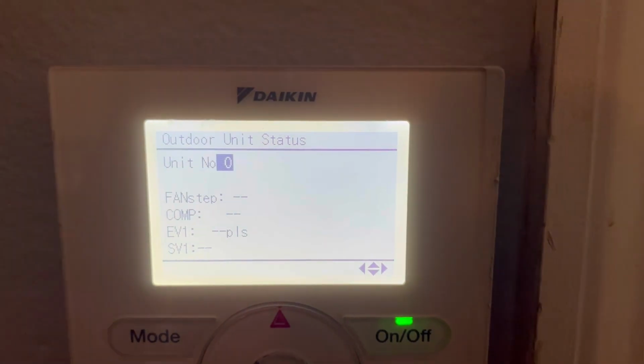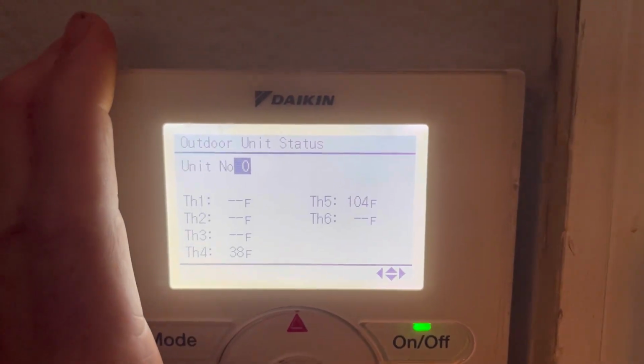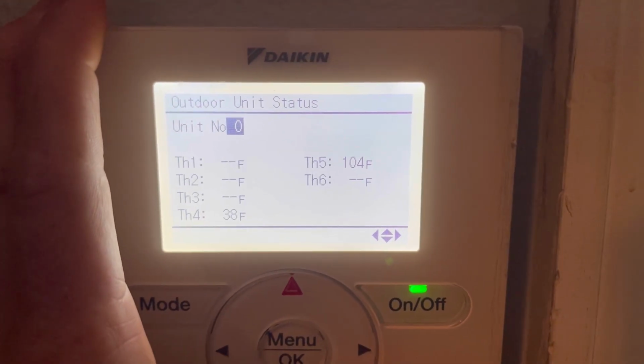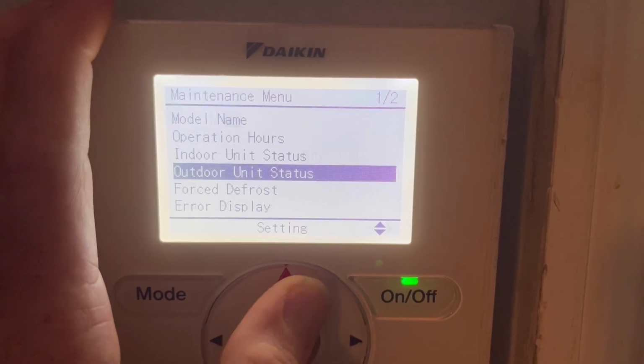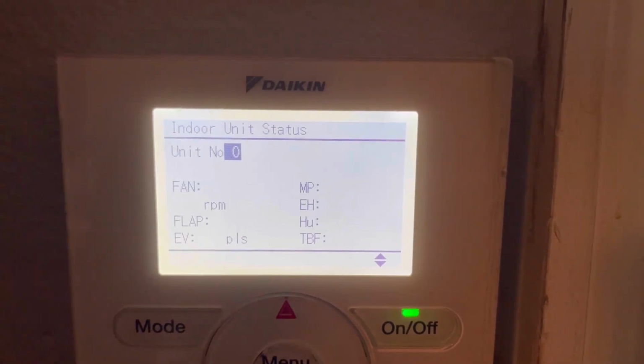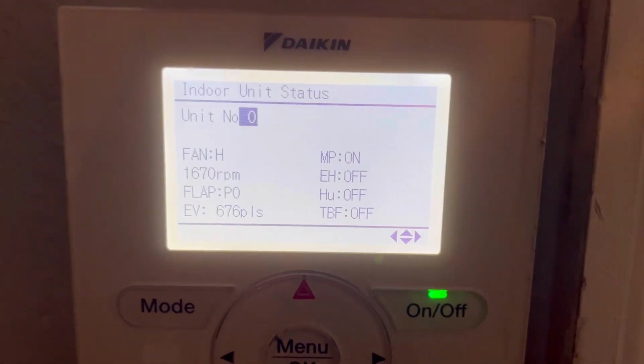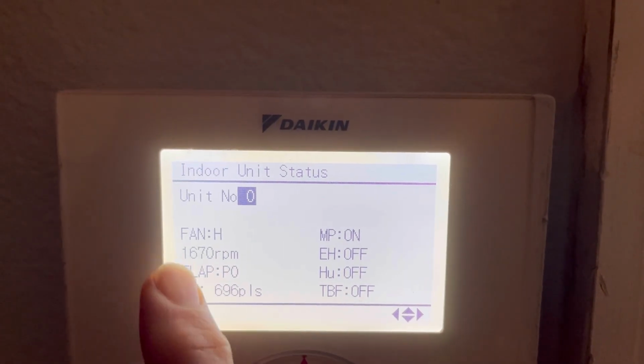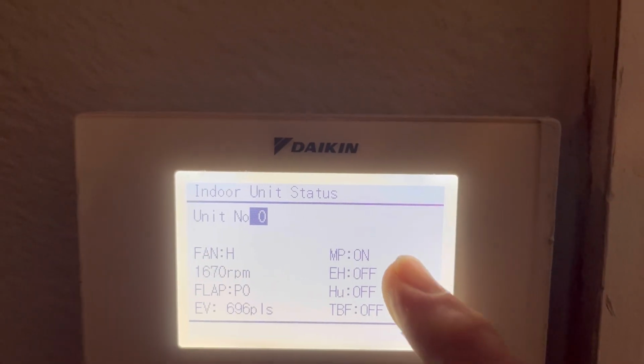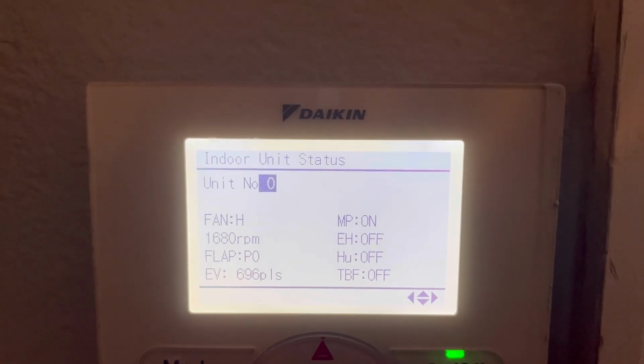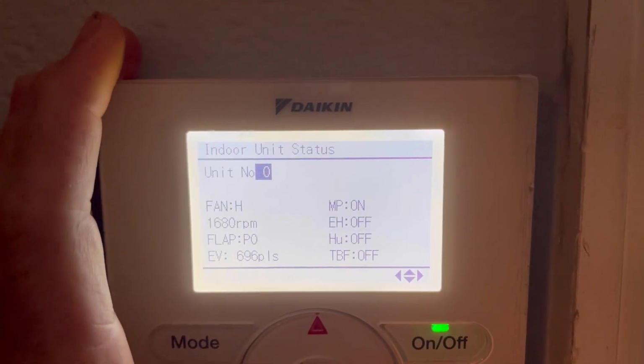These update about every 5 seconds on my system, as opposed to waiting on service checker to update every couple minutes, every 2 minutes, 3 minutes, 4 minutes. Indoor unit status. This is why I like maintenance menu. It tells me my valve pulses, my fan RPMs. I'm set to high. Any of my safeties that might be tripped or set or even off, I can see all of those registered here.